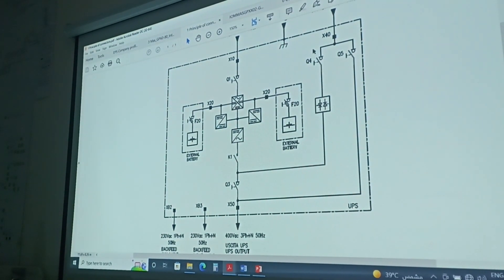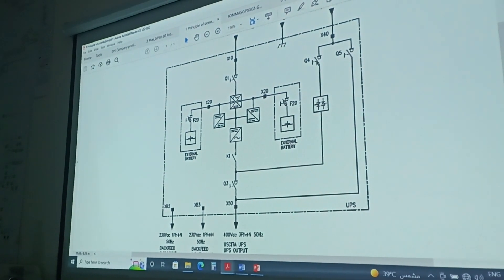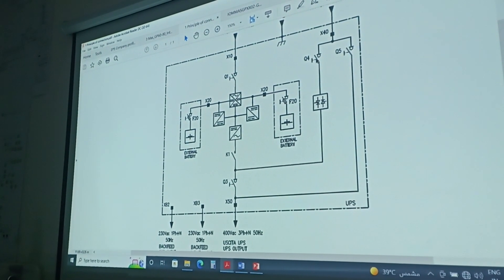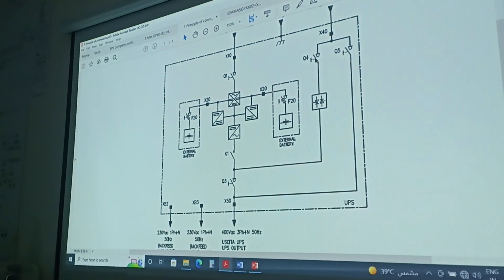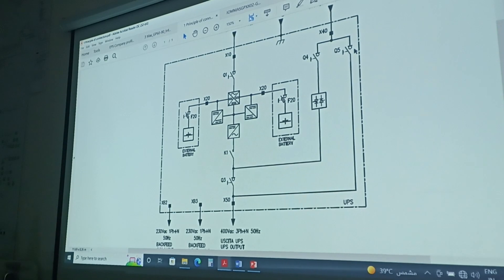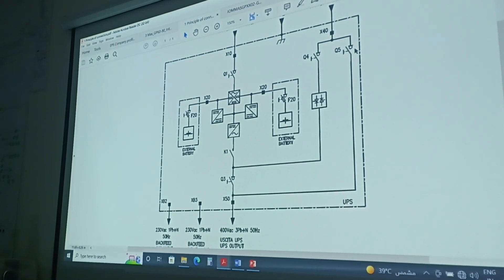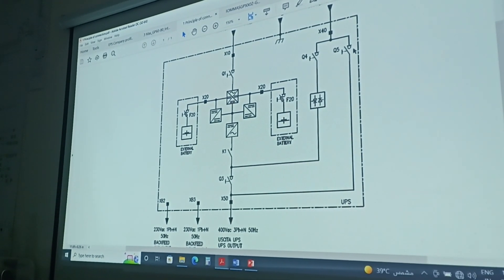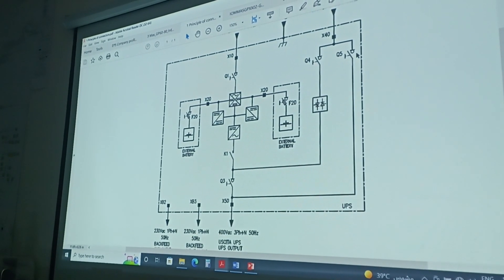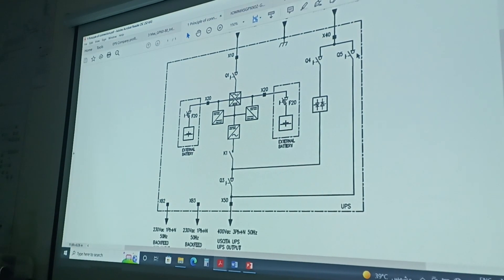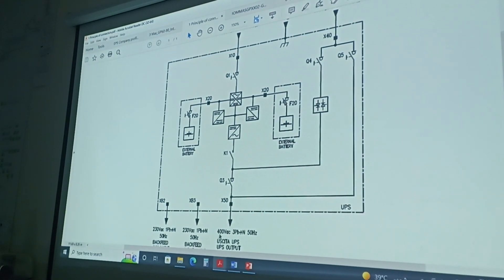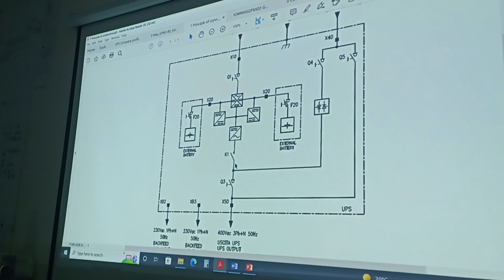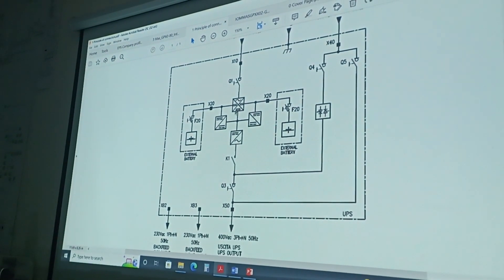We have two types of bypass. One is the static bypass, or sometimes we call it automatic bypass. And here is the manual bypass for maintenance bypass. In case of doing some maintenance, or if you want to isolate the UPS, you'll connect to the maintenance bypass. And here we have that output connection to the load in case of loop.